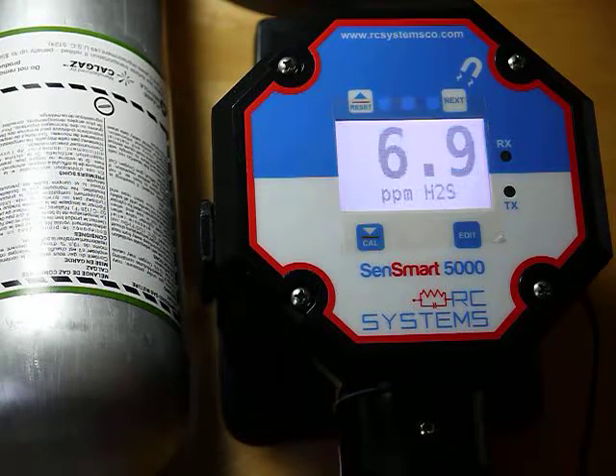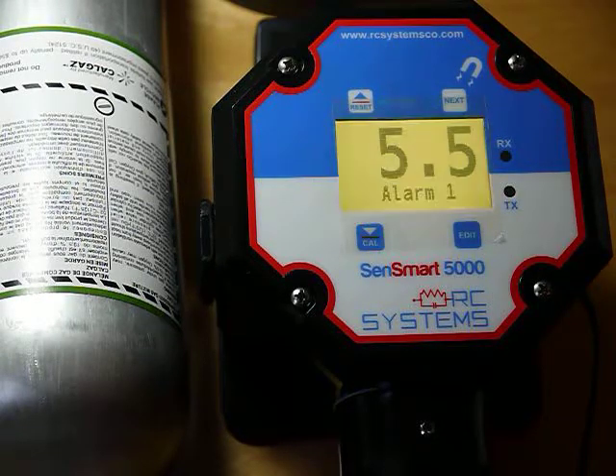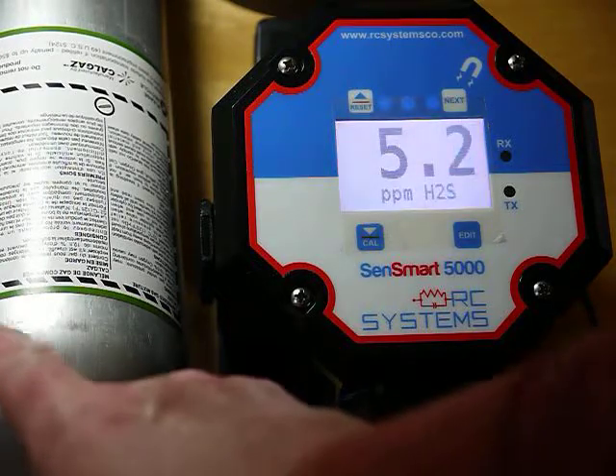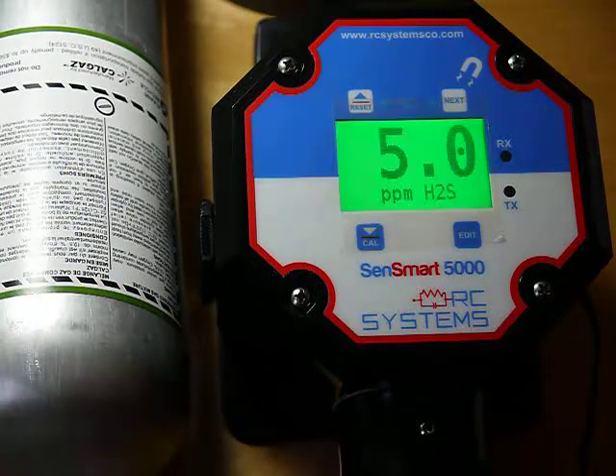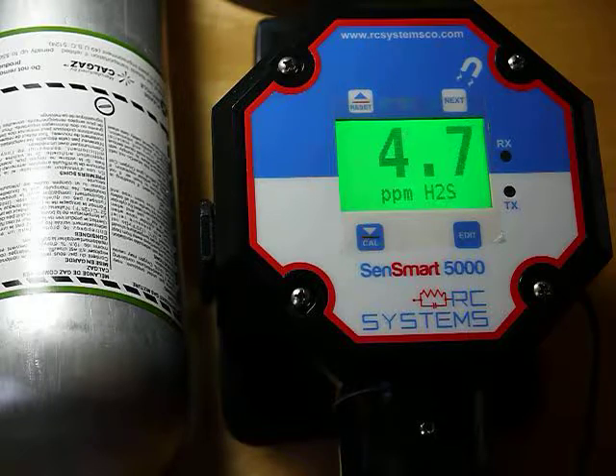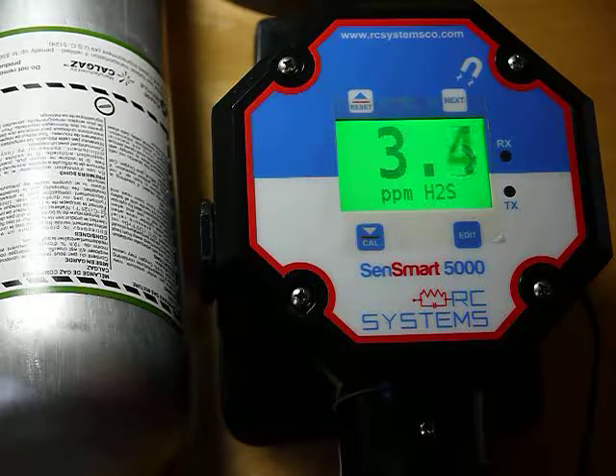For calibration, we went through those steps. We showed it what clean air was like. We hit edit and accepted it. We put on a known standard, a valid calibration gas of 25 ppm. We watched it till it was stable, and then we accepted it. So that's electronically adjusting the sensor. The sensor is almost like a little battery. Every time you calibrate it, it may need to slightly adjust the gain. Eventually it won't be able to do that, and that's when you have to replace the sensor.